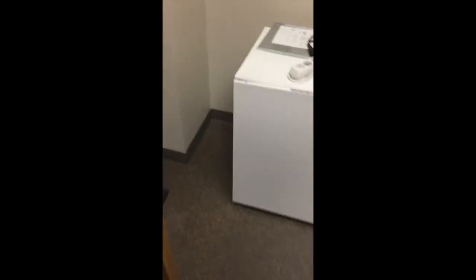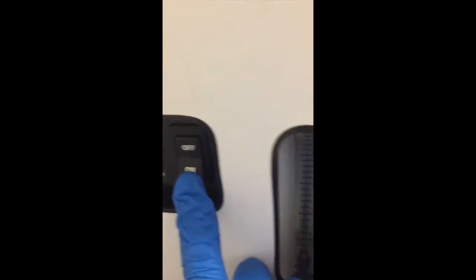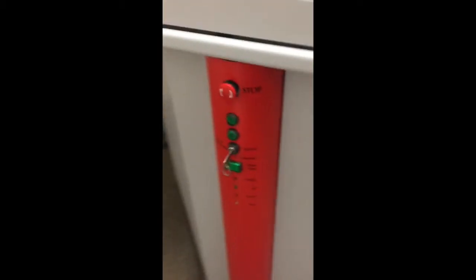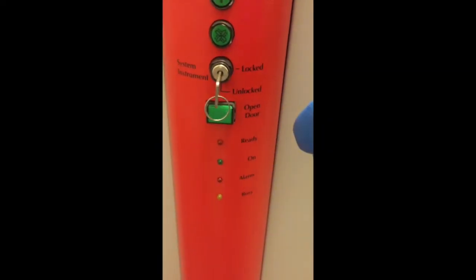Okay. So first thing we do is to go over here and turn on the chiller. This will start circulating the chilled water to the X-ray source, which is right there. And make sure this key's unlocked right here, straight up and down, not turned sideways. And these knobs here, the red ones, are emergency stops. So initially when you test, it's on both sides. And okay, we're not going to talk about this yet. Right, how to turn it on.